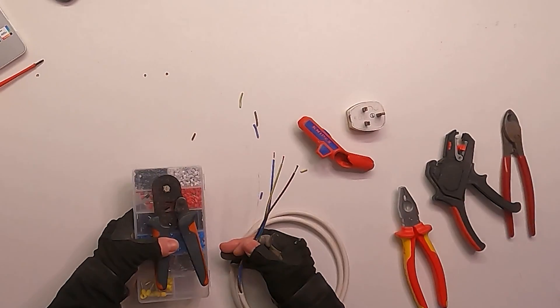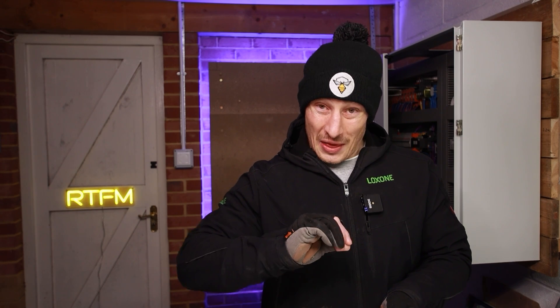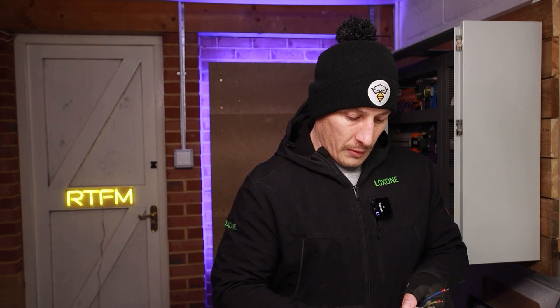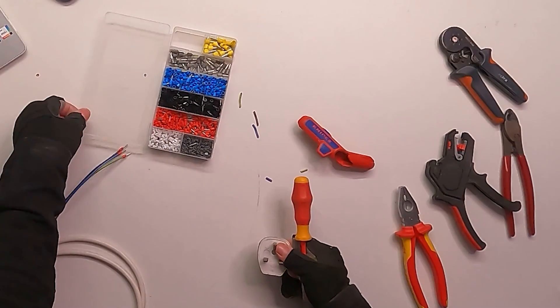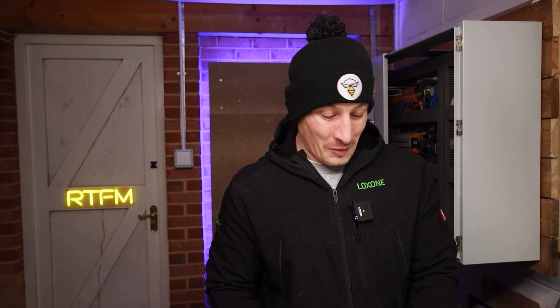The final tool is this ferrule crimper with a set of ferrules — just from Amazon, nothing too expensive. I don't think you really need to go as far as paying £100 plus for the Knipex version. Notice that I'm not twisting the copper — twisting it actually thickens the core and makes it harder to get into the ferrules, so just slide them straight on. Crimp them with the ferrule crimper: one, two, three. That's one end done. Remember to close the box on your ferrules, because we've all experienced ferrules getting knocked over and having to sort them all out.